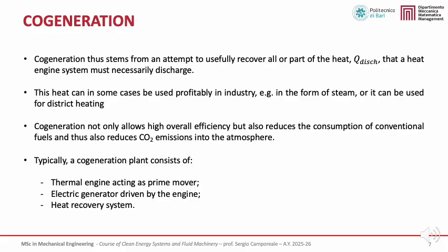In this slide, we introduce the concept of cogeneration. Cogeneration is based on the idea of recovering all or part of the heat that a heat engine must inevitably reject during operation. Instead of being dissipated to the environment, this heat is recovered and used in a useful way. In many cases, the recovered heat can be used in industrial applications, for example as steam, or supplied to district heating networks. Cogeneration allows a much higher overall efficiency and reduces fuel consumption, leading to lower carbon dioxide emissions.